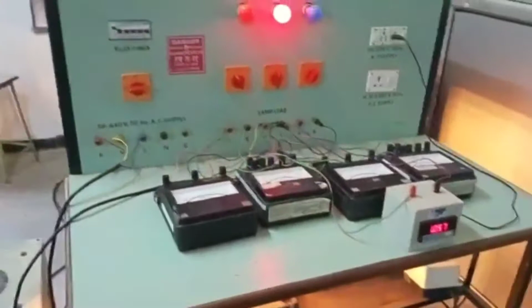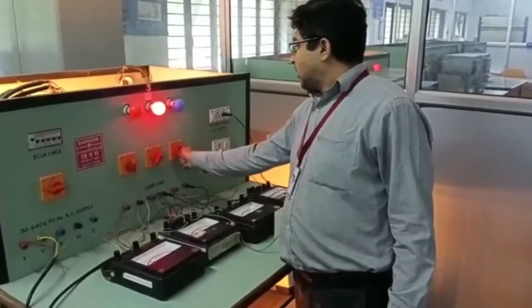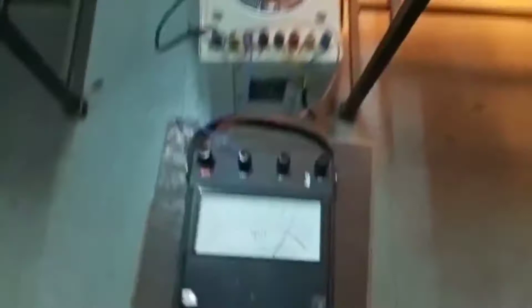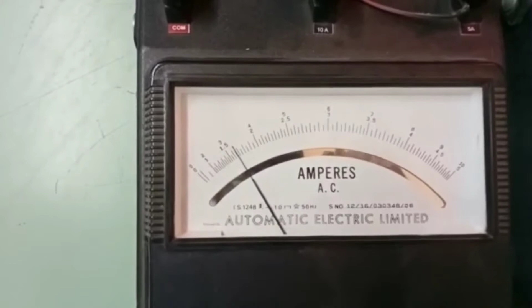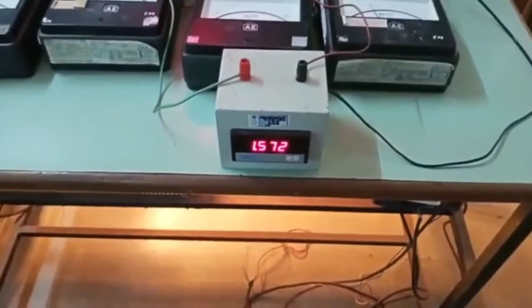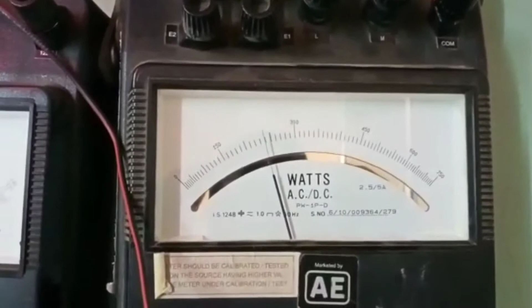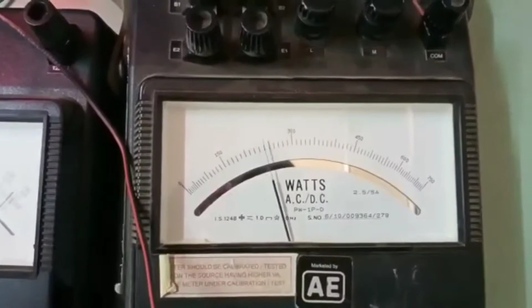Now we are going for the next unbalanced switching position. Here I put this on third position, while the second Y phase is on fourth position and the B phase on fifth position. Under this unbalanced condition, again the line voltage is 415 volt. The phase voltage is 234 volt. The line current is 1.65 ampere. Phase current is 1.572 ampere. Wattmeter W1 shows 130 watt. Wattmeter W2 shows 240 watt.